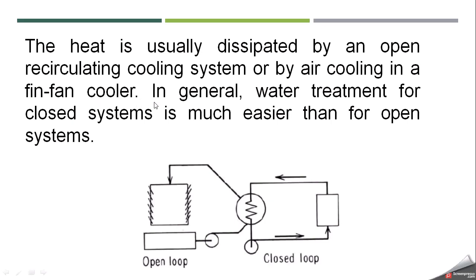Water treatment for a closed system is much easier than for open systems, which is an advantage. The schematic shows a closed loop with a pump that circulates water to the main process, where it absorbs heat. The heated water then rejects its heat to an open loop system. Two loops are involved because after the temperature increases, if we do not cool the water it will not be able to cool the main process further.